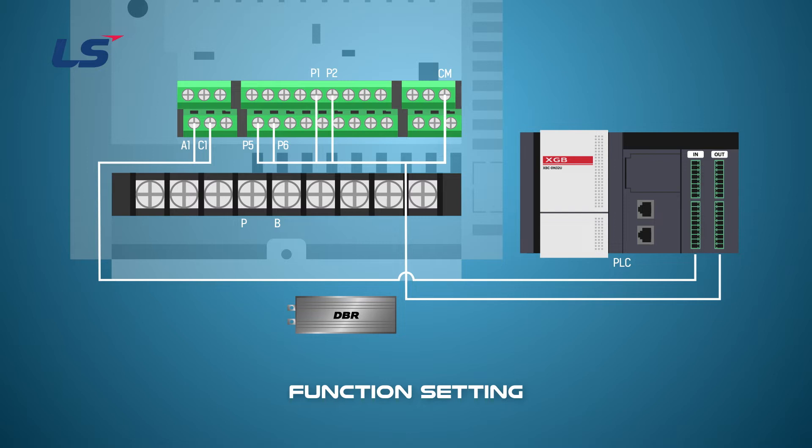In the case of IS7, the brake unit is not built in from 30 kW or more, so please check the inverter capacity and attach the brake resistor after installing the brake unit.